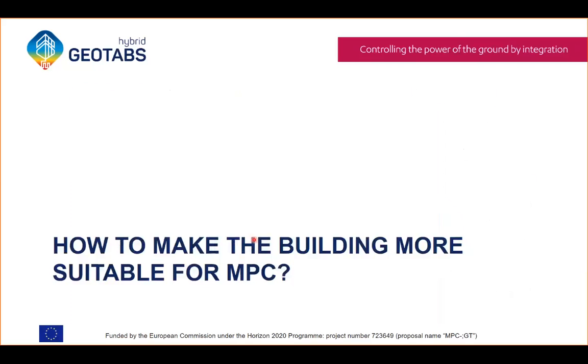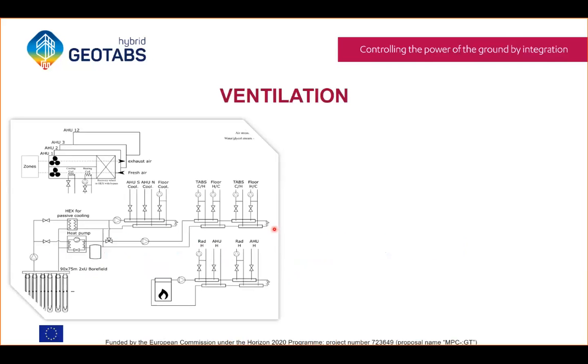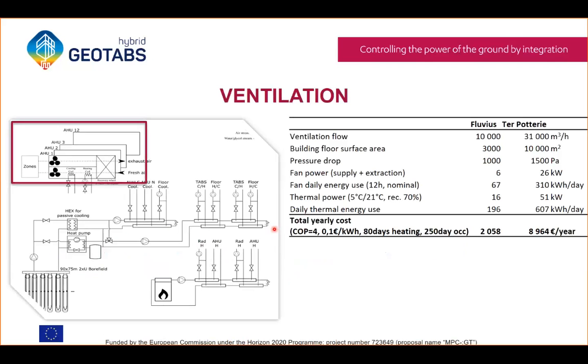So let's dig now into the main part of this presentation, which is for HVAC engineers: what should be taken into account in the design to make the building more suitable for MPC. I would like to start with ventilation, and I hope you will allow me to make some quick and maybe dirty estimation of cost, just to give a feeling of what is at stake. These numbers are inspired from the Fluvius and Ter Potterie buildings, and we see that they both have a substantial amount of ventilation: Fluvius 10,000 and Ter Potterie 31,000 cubic meters per hour.